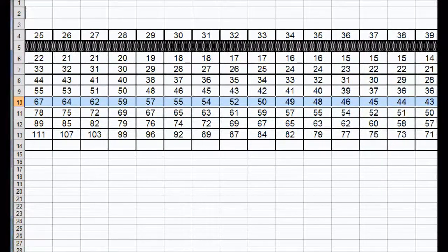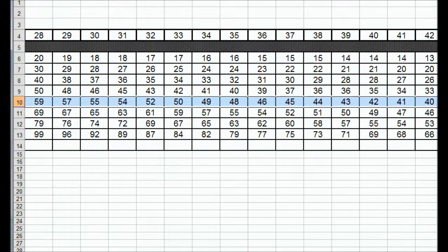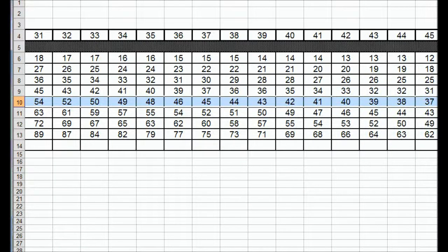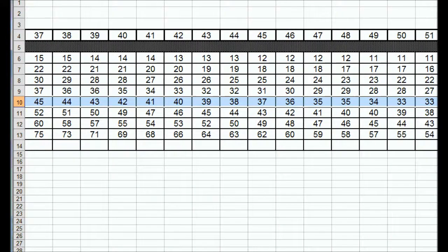We jump to 35 SEER and there's only $7 worth of gains from 30 SEER to 35 SEER. So the gains really aren't that much. They're harder and harder to come by as time goes on. You'll see that between 43 and 44 SEER, the difference is $1. So it gets harder and harder.